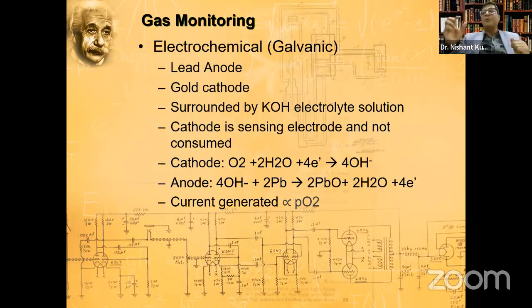Usually it is supplied in a vacuum pack. The moment you open it, it will start working and the lead anode will start getting consumed. Over a period of time it gets weaker, and that's why you have to change it every 6 months, in all the anesthesia machines. If you're buying an anesthesia machine, the paramagnetic will be costlier, but that will last you a longer time. So electrochemical, if not in use, please let it be exposed to the lowest concentration of oxygen possible, that is, leave it to air rather than keeping it in a high oxygen environment.